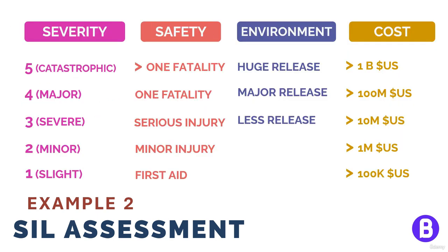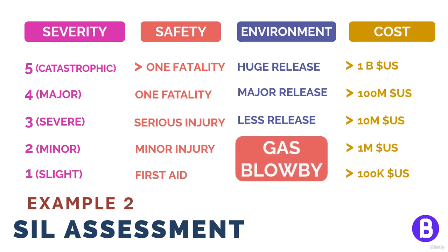What about the severity? The issue here is that the consequence can be huge. This is because we are talking about gas blow-by case where the liquid level falls and the vessel is drained from liquid. Here, the pressurized gas shall start to go to the water treatment system, which is usually operating at atmospheric pressure and cannot handle any pressure.